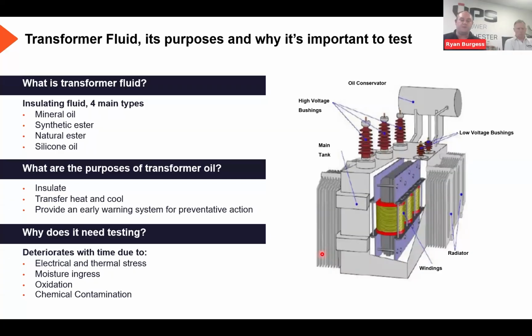Yep. So when it comes to transformer fluids, there's 4 main options out there that you can use. First of all, you've got mineral oils, then you've got synthetic esters, natural esters, and silicones. All the fluids perform essentially the same jobs. It's just certain situations where you may choose one over another. So, for example, if it's an asset in an indoor space you may go with a synthetic ester due to it having a higher flash point and fire point, meaning that if it does catch fire, it takes a lot higher temperatures for that fire to catch hold. And as well, in turn, you can then make the transformer smaller because you don't need as much of the fire prevention systems as you would with a mineral filled asset.